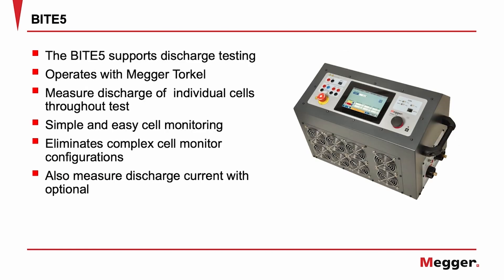The BITE5 also supports discharge testing and can be used with a Megger Torkel. It will measure the discharge of individual cells throughout the duration of the discharge test. This allows simple and easy cell monitoring. The BITE5 will also measure the discharge current if the optional CT is used.